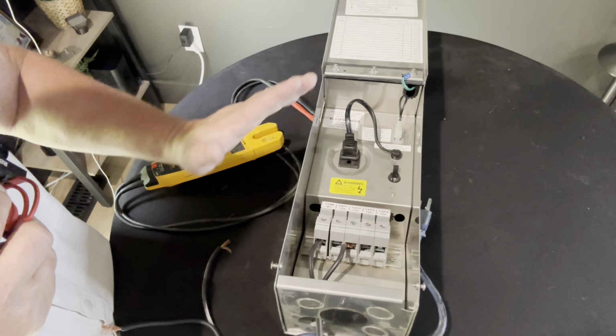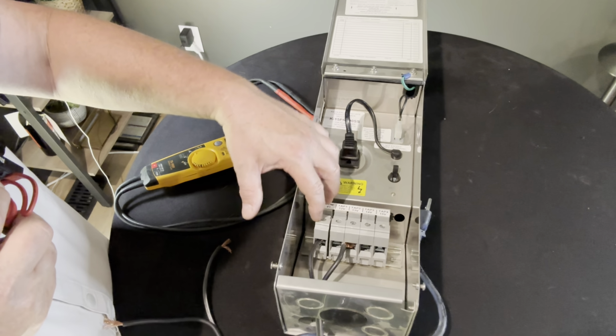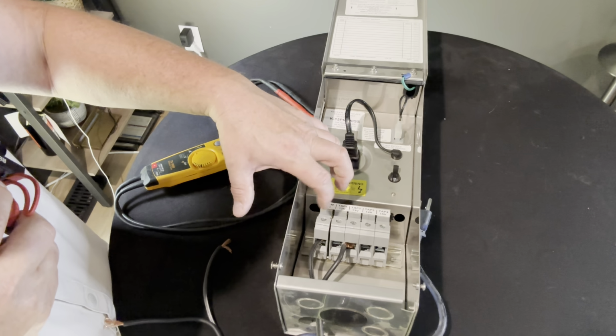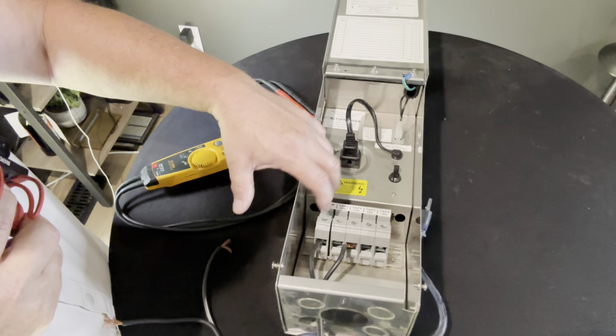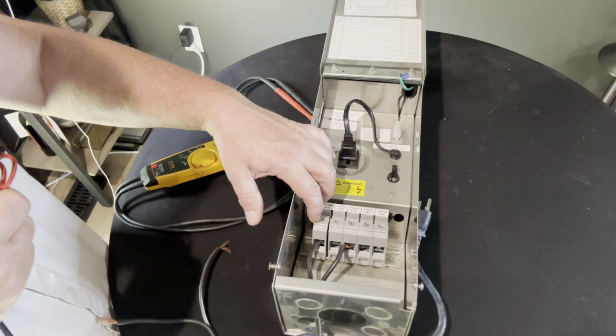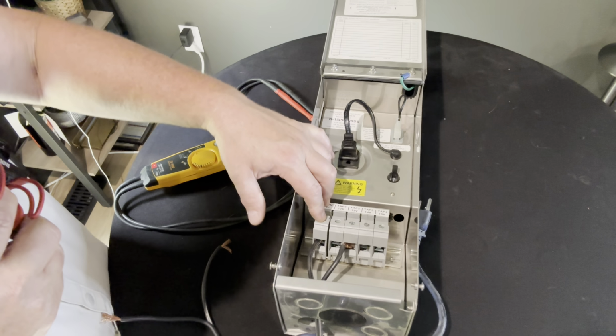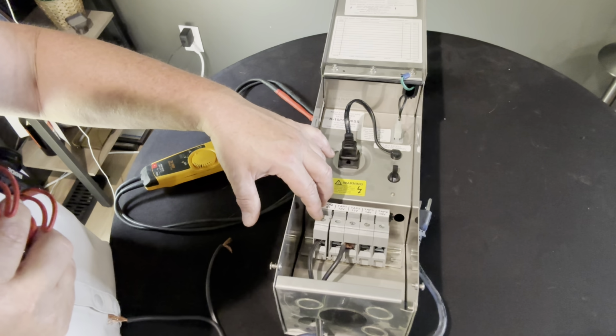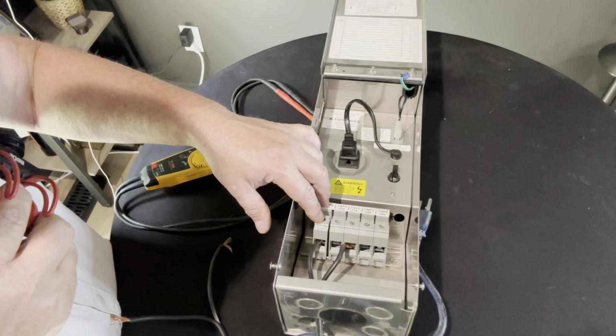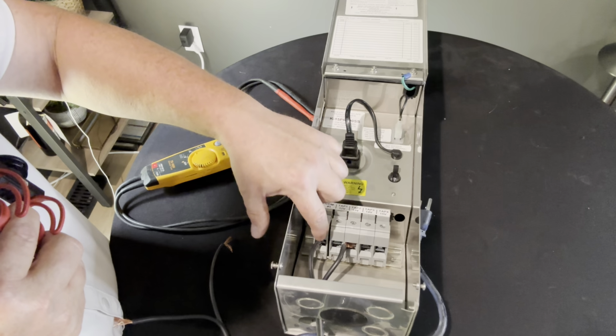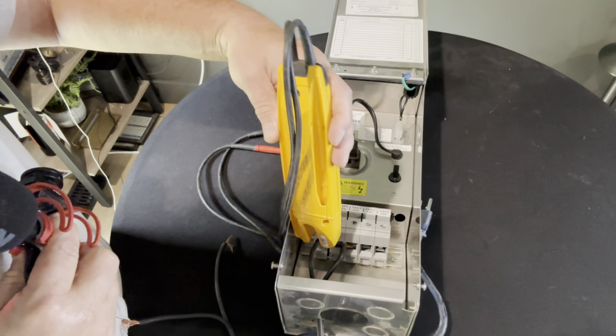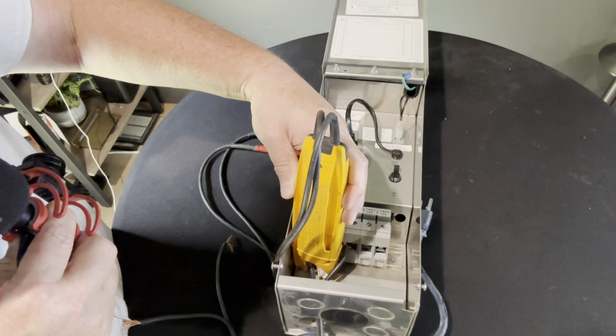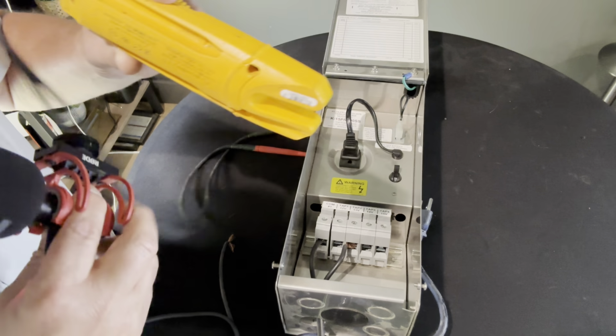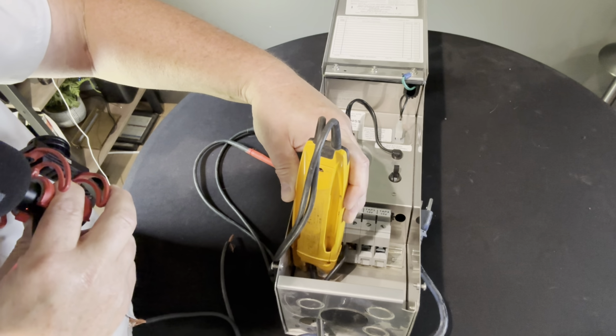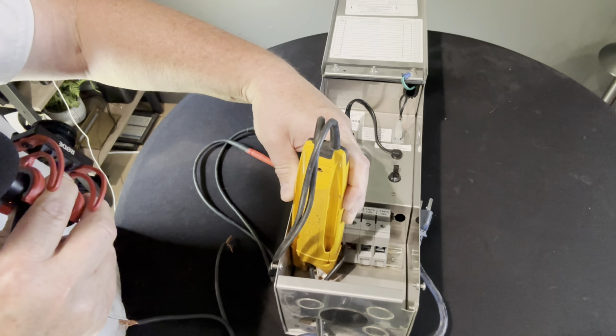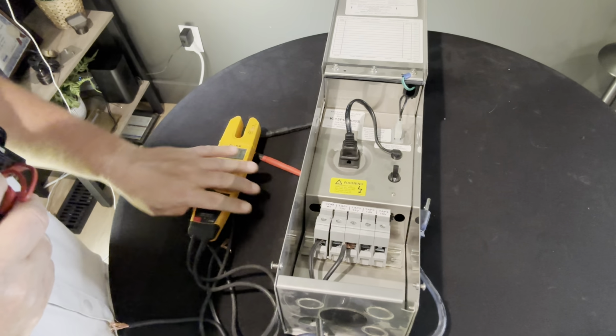On the COM, so we're talking about all the wires that go into here, you want to stay right around 24 amps, 25 at the most, but I believe the rating is actually just 24 amps on the COM. Now, typically we're not loading them up that close, but in the event you have 3, maybe even a 4th wire, or you've got a lot of lights on some long wire runs, you want to make sure all the wires that come into here, if you were to go down and do it, you can test all the wires at once. That way you don't have to add them up individually. You just put your meter once again over half of all the wires, and it will give you what that reading is. And as long as it's 24 or less, you're going to be okay.